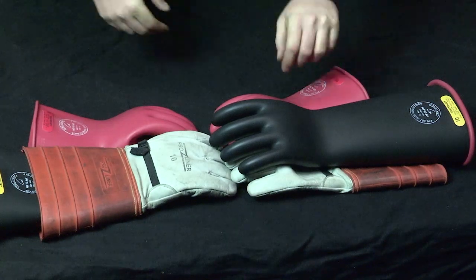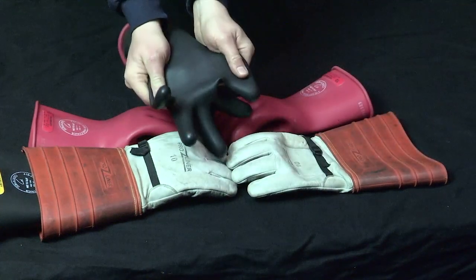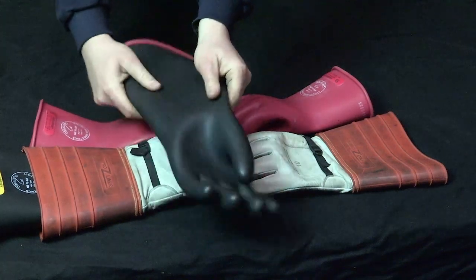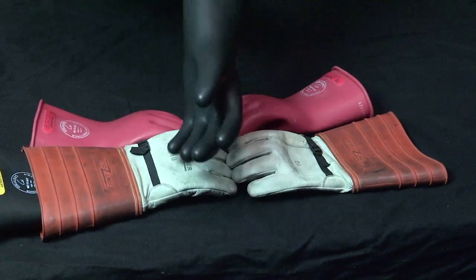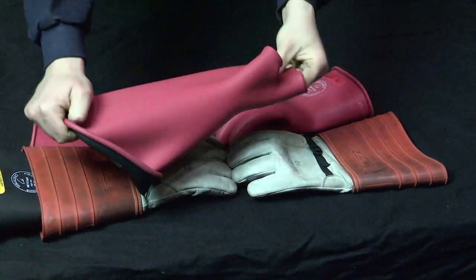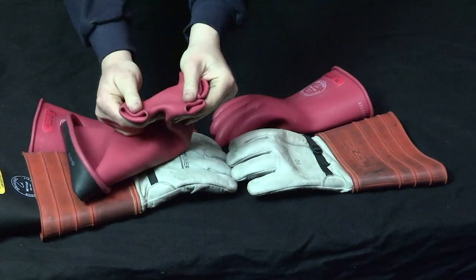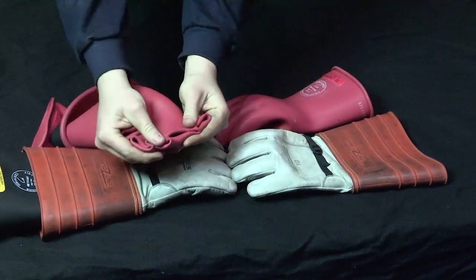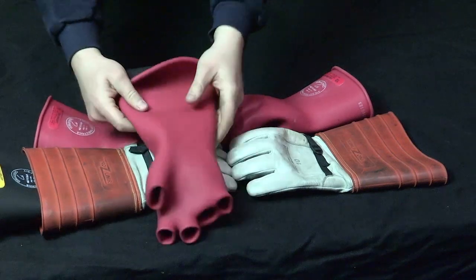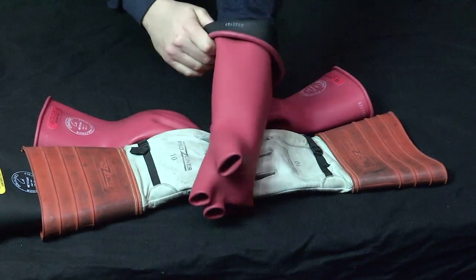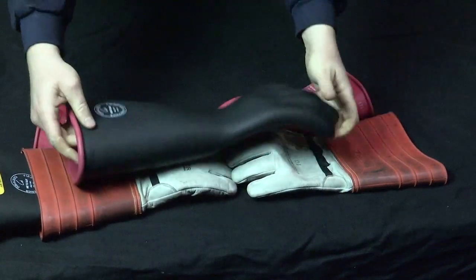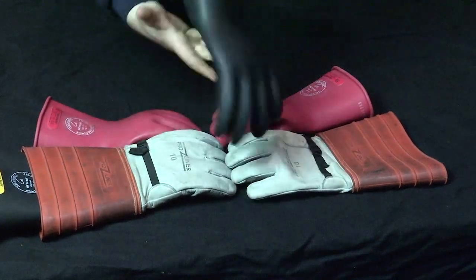A visual test tells you if there is excessive wear. Stretch the glove to look for cracks and tears. Reverse the glove and do the same on the other side. Check between all fingers. Look for punctures, hard spots, foreign material, or breaks in the surface. With the two colors, these abnormalities are usually easy to see.